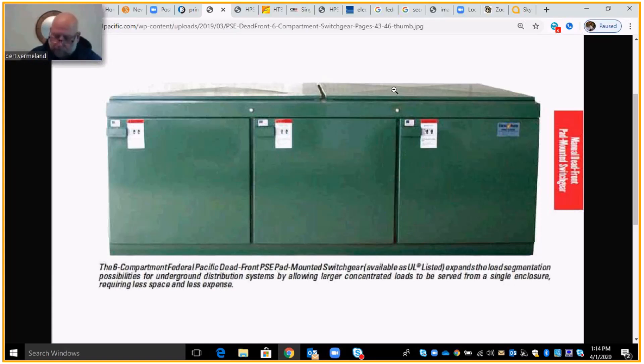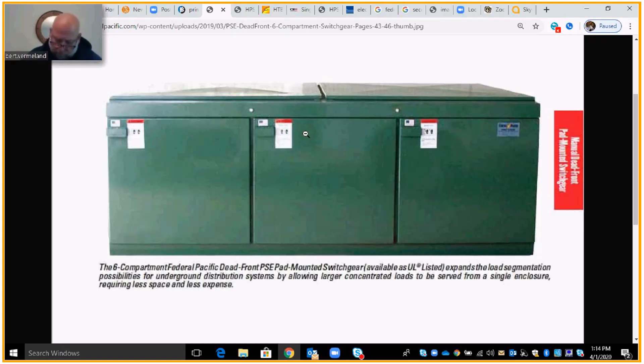One, two, three on one side and one, two, three on the opposite side — not visible because it's turned this direction. If you look at your underground distribution standards manual, attached to the D2L assignment, you'll find the switchgear numbered. I'll use six, four, two as the example. Six designates total compartments — one through six on the backside. Four is the amount of feeder switch locations. A feeder switch is a dead blade disconnect switch. And two designates taps.